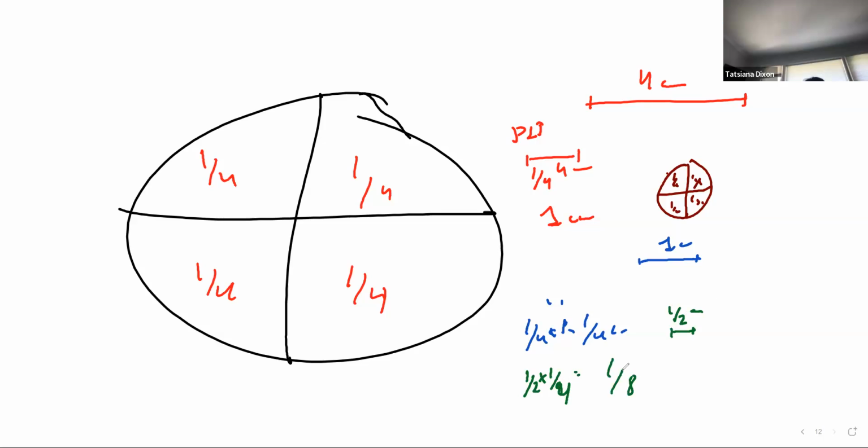But you're talking about the matching layer, right? Not PZT. Is it the matching layer or PZT you're talking about? It's the matching layer. Right now we are talking about the thickness of your matching layer.